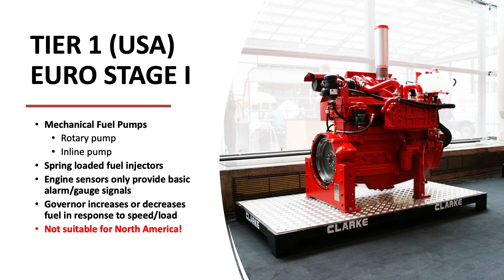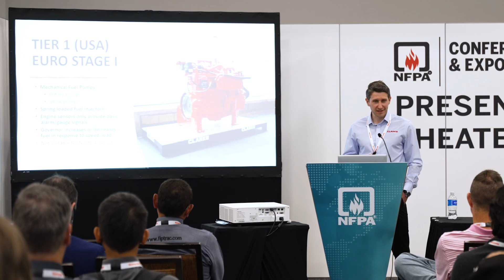These engines have mechanical fuel pumps, meaning they're basically geared straight to the crankshaft of the engine and rotate in time with it. You can have either a rotary or inline fuel pump, with basic spring-loaded fuel injectors. There are engine sensors, but it's very basic technology, mainly to satisfy NFPA 20 for alarms and signals. There's a governor in the engine which controls the speed fluctuation between different pump loads. Importantly, these are not suitable for North America, as they don't meet the emissions requirements for this region.